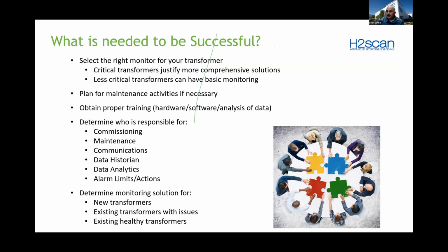Having one or two people say, "Oh, we need to put a $100,000 monitoring system on our transformers, but we're not going to be responsible." And then the maintenance guys say, "Well, we don't have time." I've seen $100,000 monitoring systems out on transformers that were never commissioned because nobody wanted to take responsibility for them. So, of course, you don't want to let that happen.